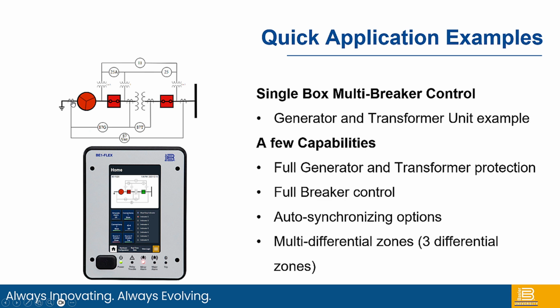Additionally, I can have a supervising unit differential that's looking around the whole thing, and that way I'm additionally protecting this breaker and also giving the ability to have tight set differentials around the individual resource. Mix and match these functions however you wish. Again, current and voltage sensing locations are one of the key pieces that allow this to do a whole bunch of these things. If you want to do synchronization, sync check, 11 is the multifunction device. So again, whatever you want to put into it, you can put into a protective relay, a single box protective relay.